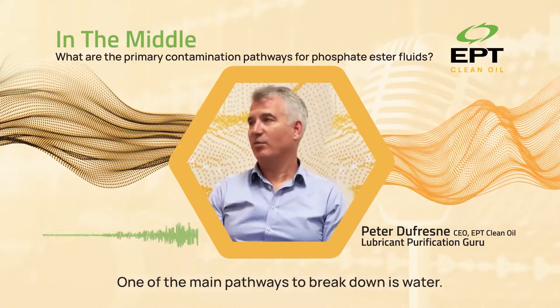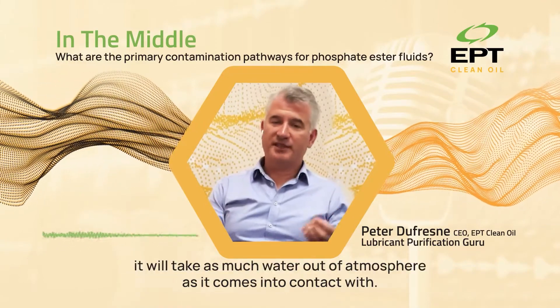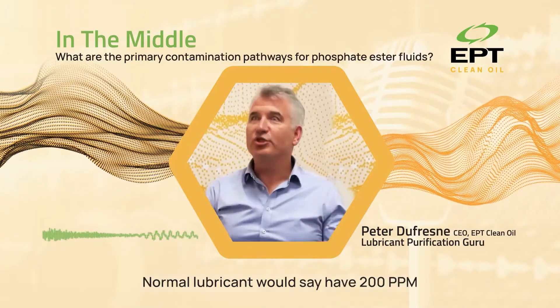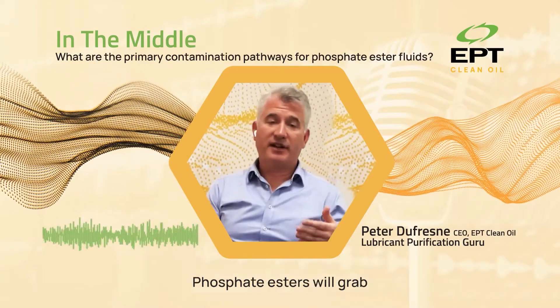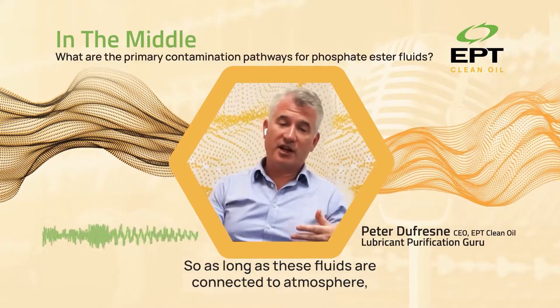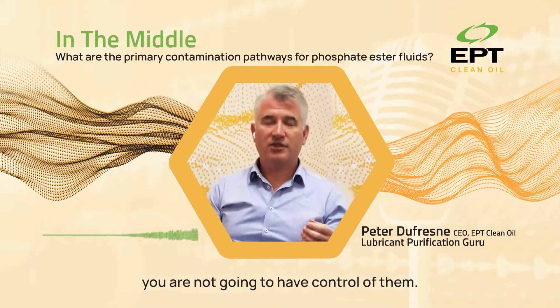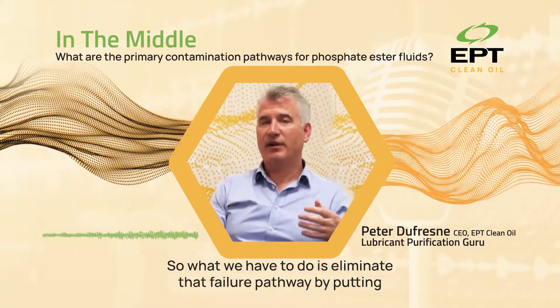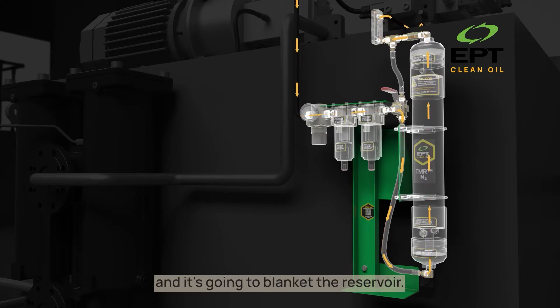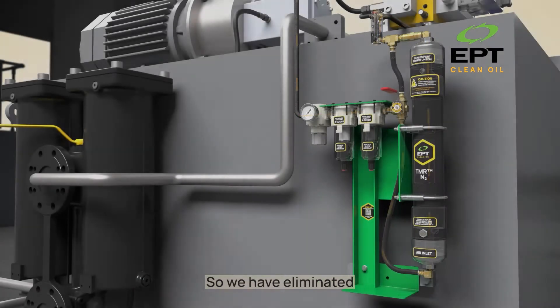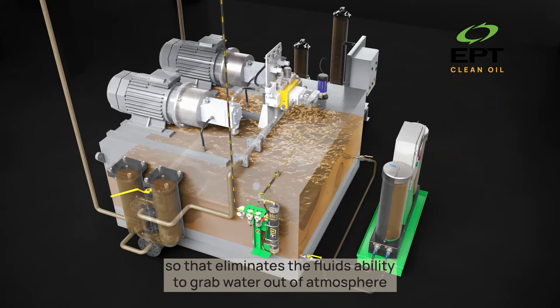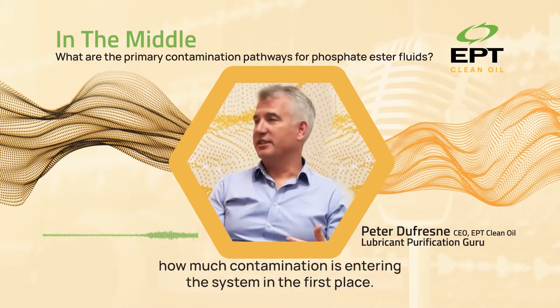One of the main pathways to breakdown is water. Because of the unique fluid properties of phosphate ester, it will take as much water out of atmosphere as it comes into contact with. A normal lubricant would have 200 ppm considered extremely high in a lube oil application. Phosphate esters will grab 2,000 ppm out of atmosphere alone, with no additional water ingress. So as long as these fluids are connected to atmosphere, you are not going to have control of them. What we have to do is eliminate that failure pathway by putting a TMR on there, which is going to generate high purity nitrogen from a regular compressed air source, blanket the reservoir, and exhaust out the breather element. So we have eliminated atmospheric contact with the EHC fluid, which reduces significantly how much contamination is entering the system in the first place.